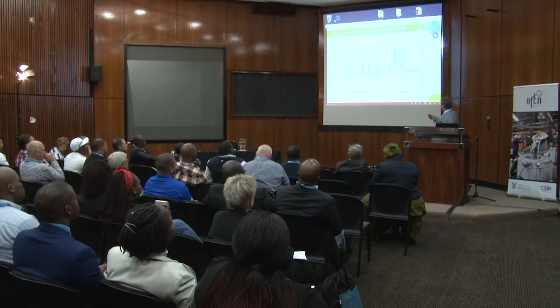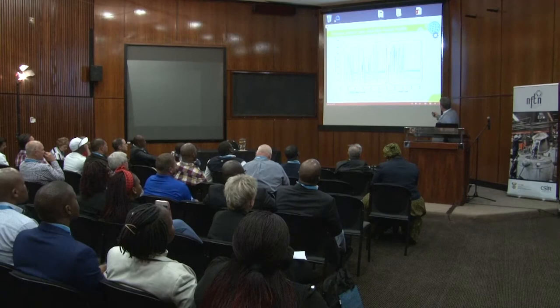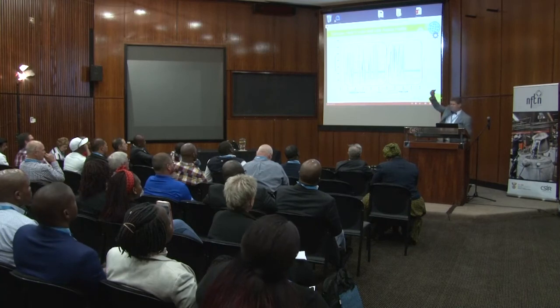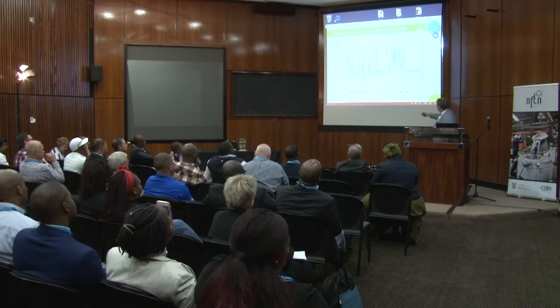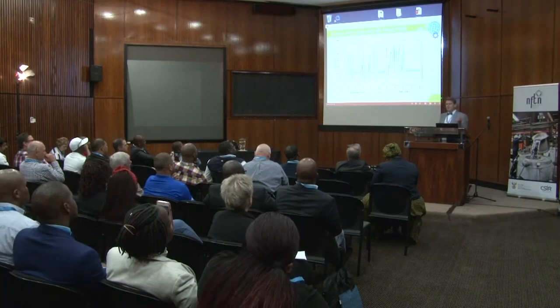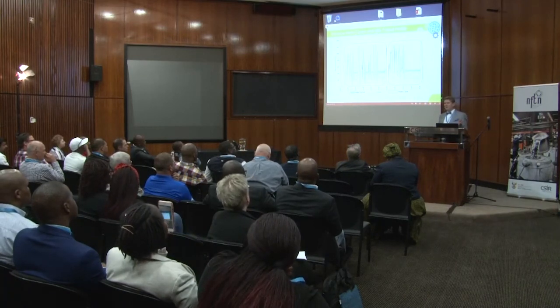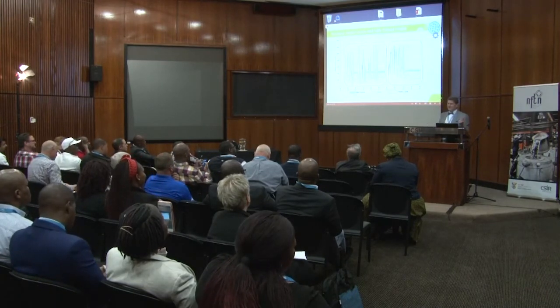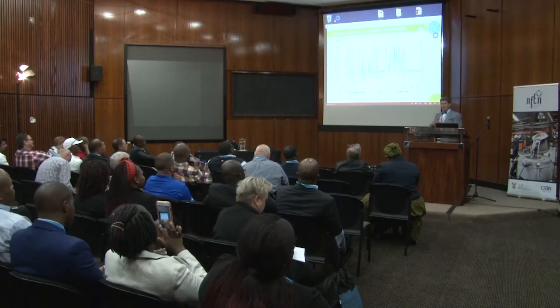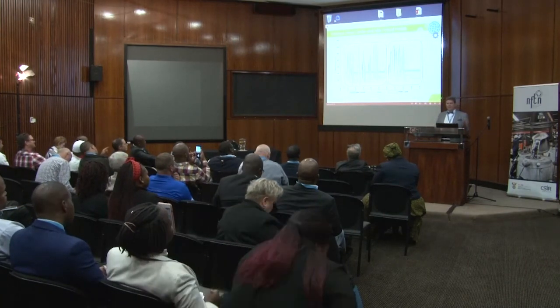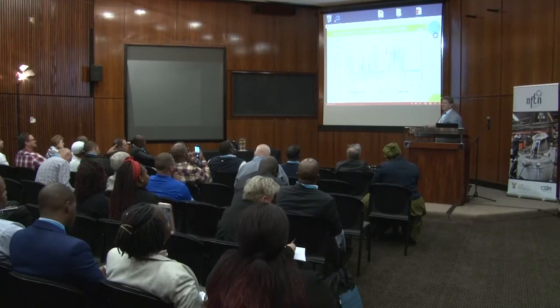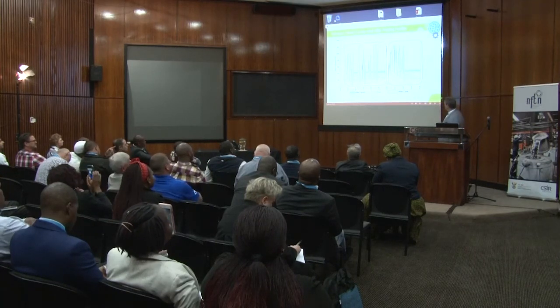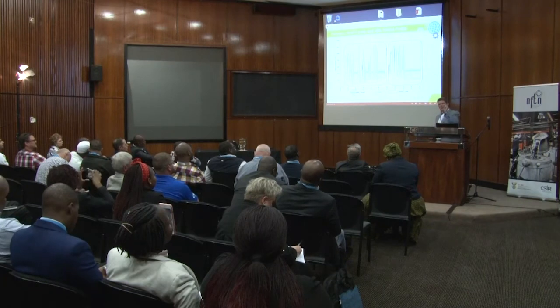The area in red represents each heat. But within each heat, as the scrap pick-up loaded scrap into the induction furnace, we found what we call idle periods. We couldn't believe the plant was having idle periods over lunch and tea time. One of the first recommendations was to have shifts overlap and not stop work during breaks. We also found, interestingly, that at night shift the idle times were longer because there were no managers present. So we started to highlight things they suspected but couldn't prove, and point out areas for improvement.